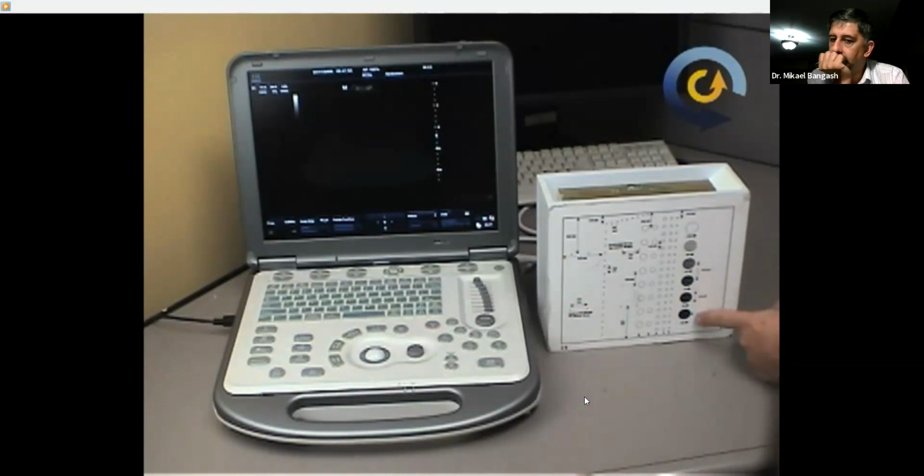There's only 6 steps across here, but you can actually watch it go from being able to transmit all the echoes through it, it'll be perfectly clear, to passing the echoes and not being able to see those on the bottom. And you want to be able to see that you've got nice gradation through here.